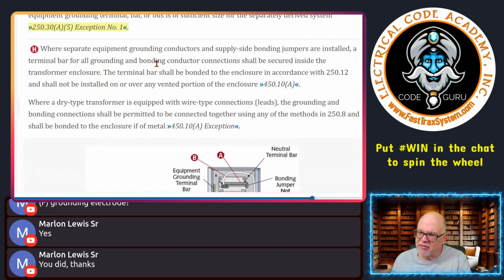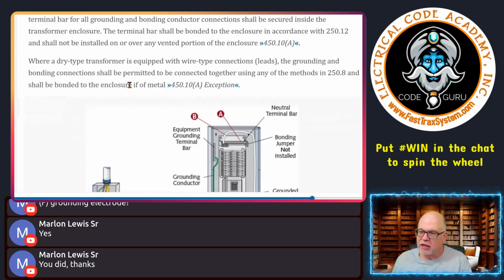It says now where a separately derived system has a separate equipment grounding conductor and supply side bonding jumper installed, a terminal bar for all grounding and bonding connections shall be secured inside the transformer enclosure. No brainer. It says the terminal bar shall be bonded to the enclosure in accordance with 250.12 and shall not be installed on or over any vented portion of the enclosure. Should be a no-brainer, although I see a lot of pictures online where the bar is just right there over top of the vent holes. And you say, Paul, it's really not going to hurt anything. I'm just telling you what the code says. You do you, but that's what the code says.